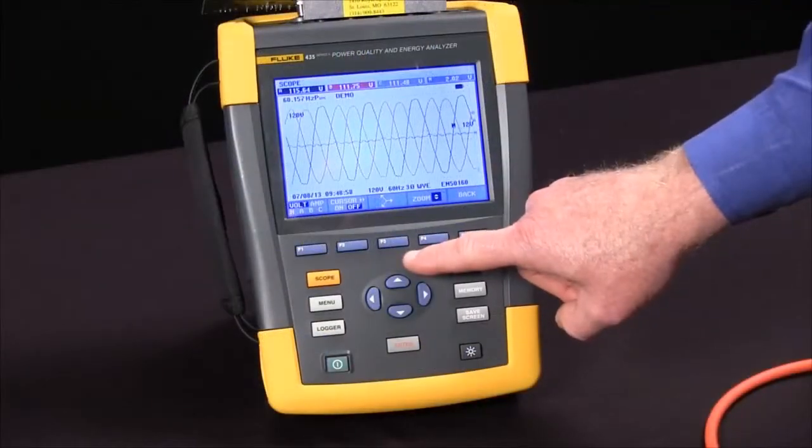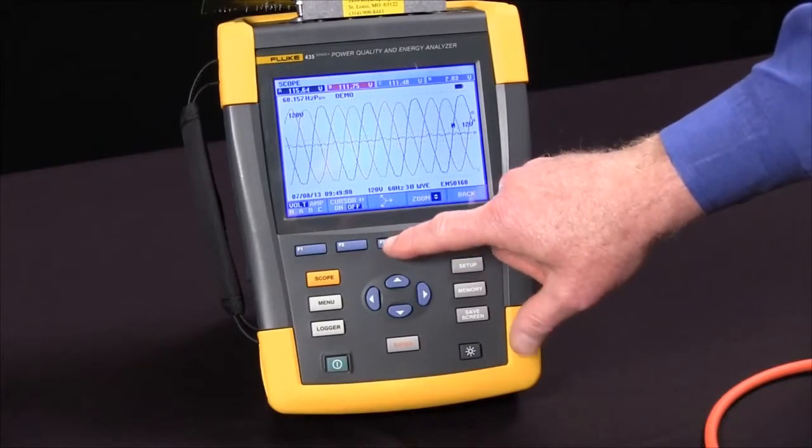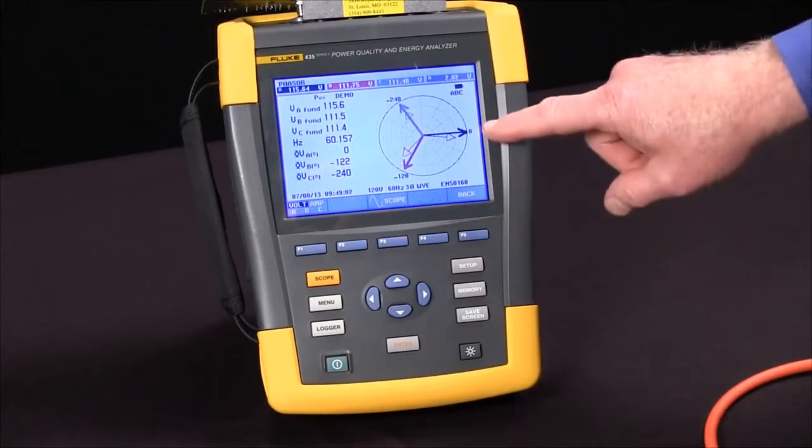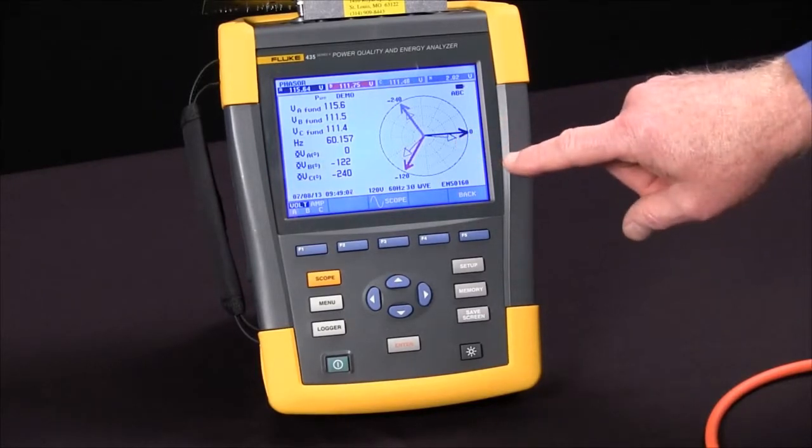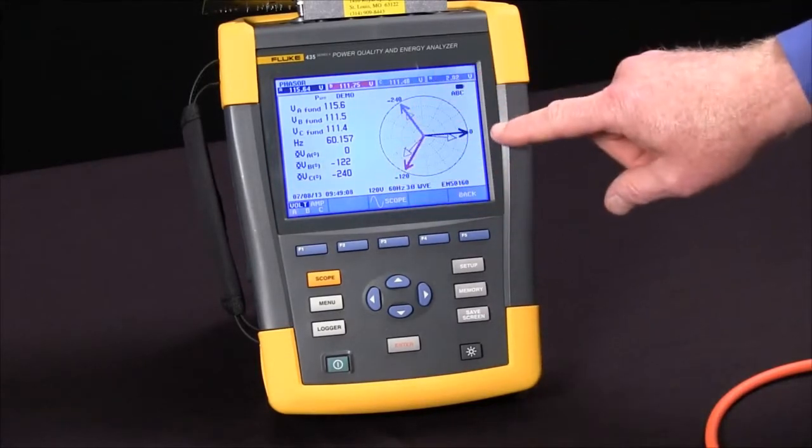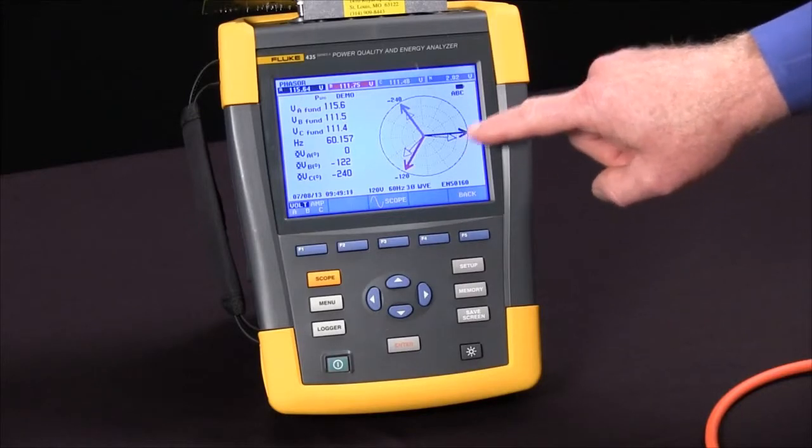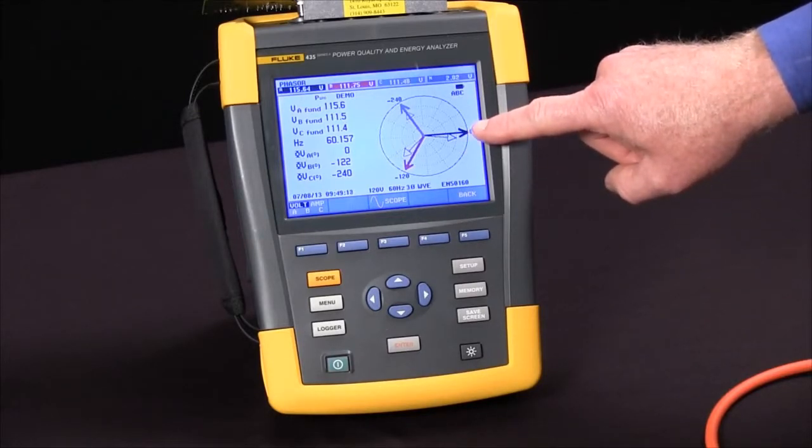If we use the F3 key to pick up phasor view, we'll see some bold vectors for our voltage and some lighter vectors for our current. If things are properly connected, we should see those vectors being close to in phase with each other.